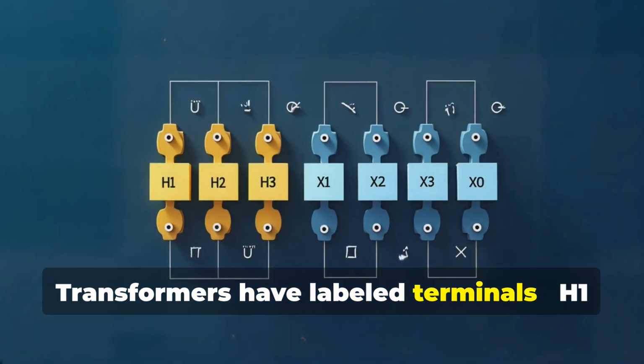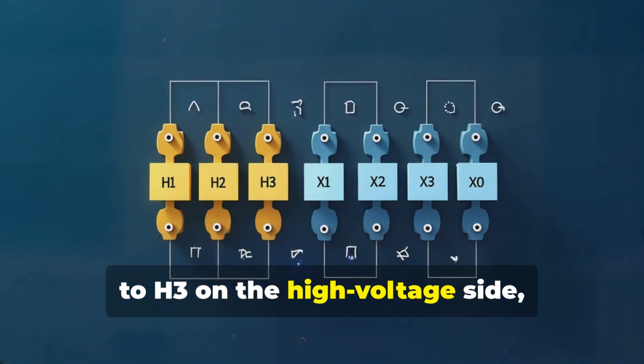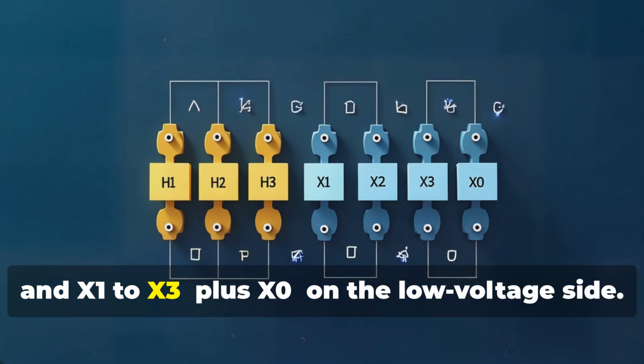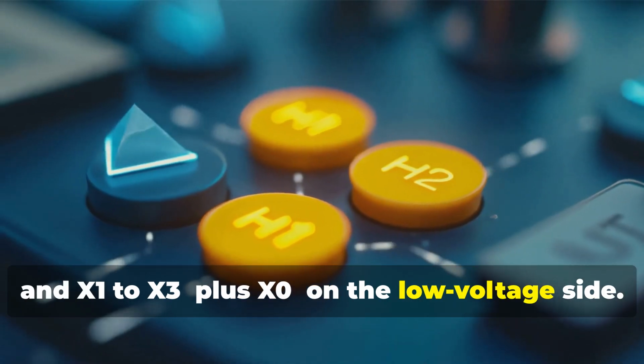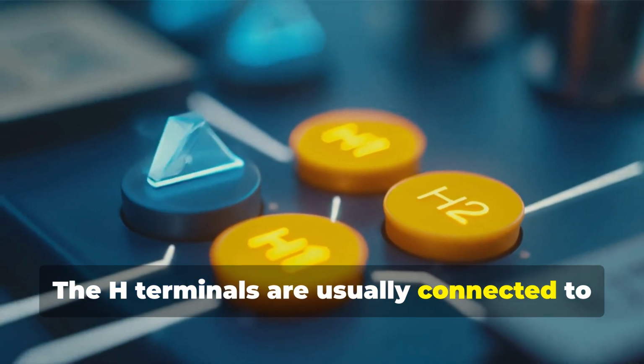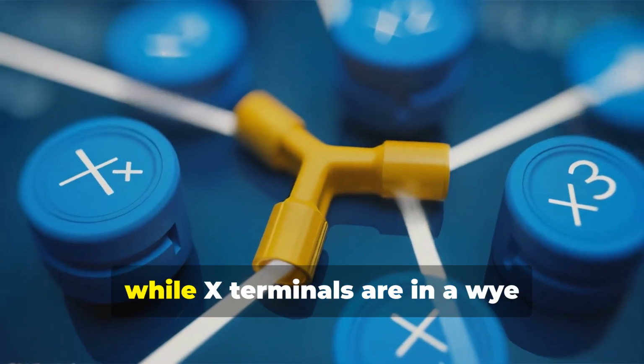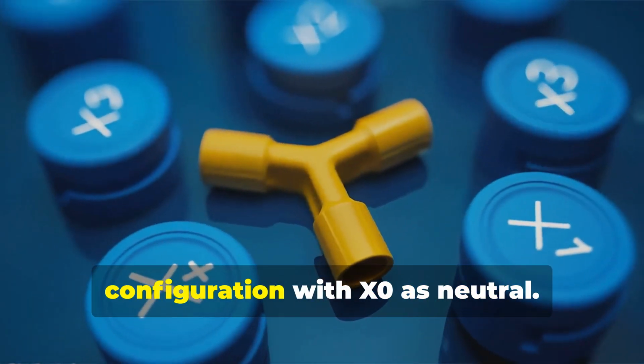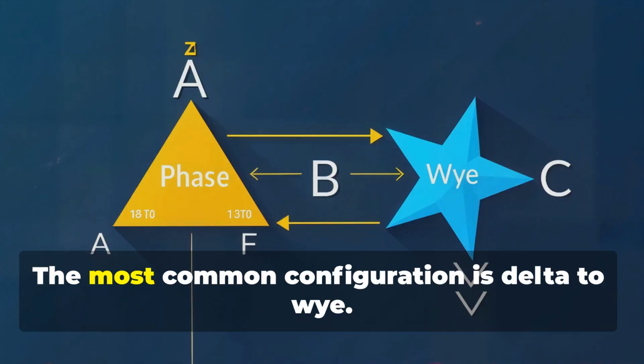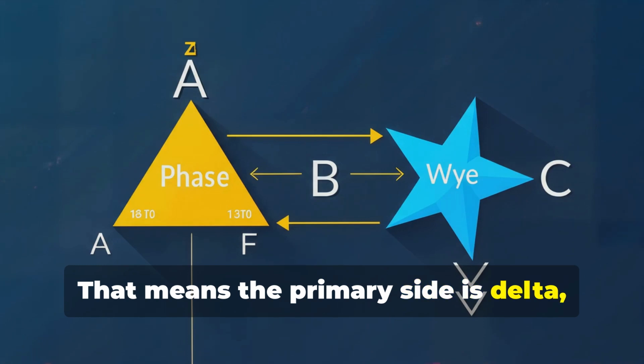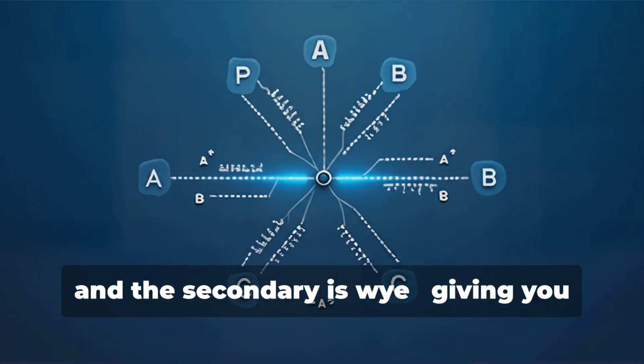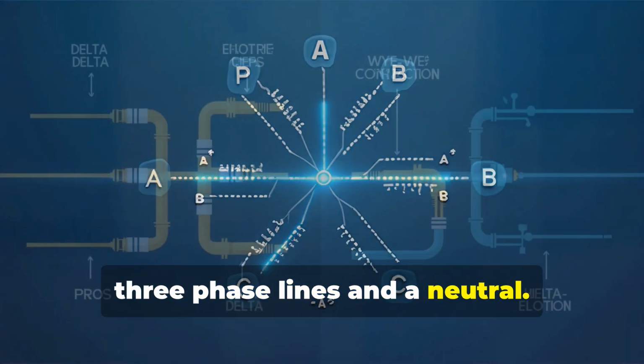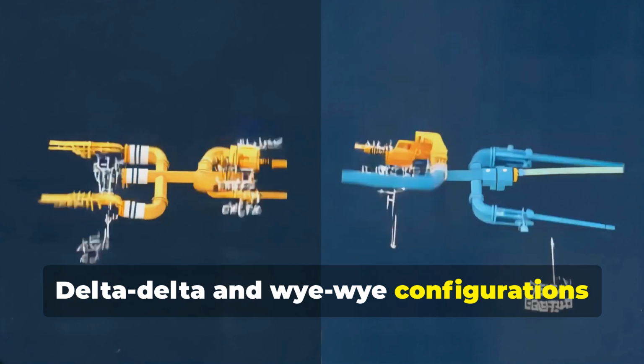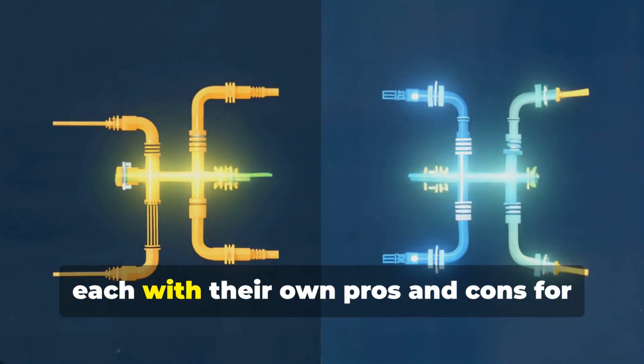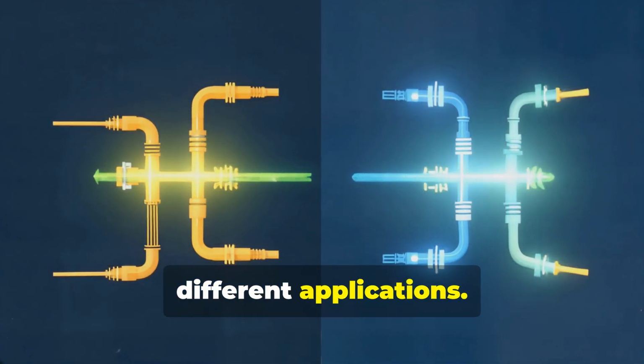Transformers have labeled terminals, H1 to H3 on the high voltage side, and X1 to X3 plus X0 on the low voltage side. The H terminals are usually connected to a delta configured primary, while X terminals are in a Y configuration with X0 as neutral. The most common configuration is delta to Y. That means the primary side is delta, and the secondary is Y, giving you 3 phase lines and a neutral. Delta-delta and YY configurations also exist, each with their own pros and cons for different applications.